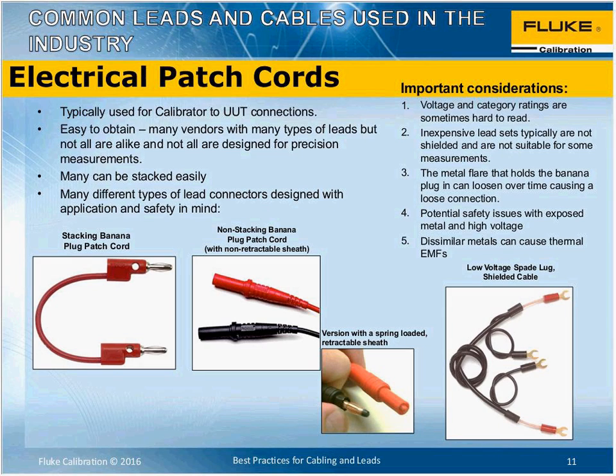Things to point out with these is that volt and category rating are sometimes hard to read, and so take the time to do the research on the lead before you use it. If it's in question, it could save your life. Inexpensive lead sets are typically not shielded, like the pictures show there, those non-stacking banana patch cords would not be shielded. What we find, as I mentioned, is a lot of times when we go visit customers, they are making high resistance measurements with those types of leads, and you'll find out through this webinar that that probably isn't the best use of those leads and can lead to measurement errors. So I guess the message here is using the right lead for the right job.